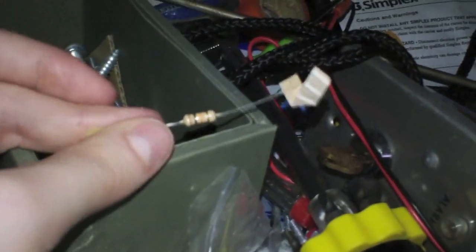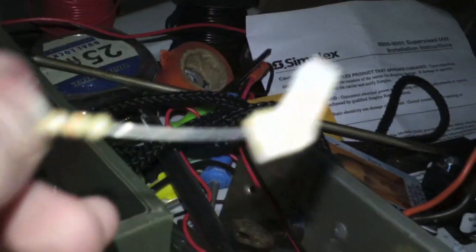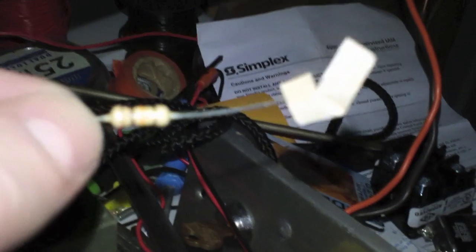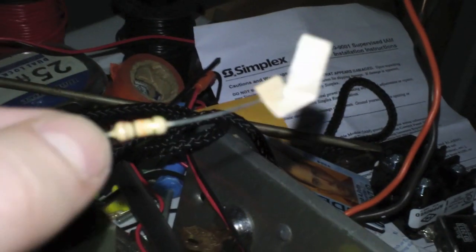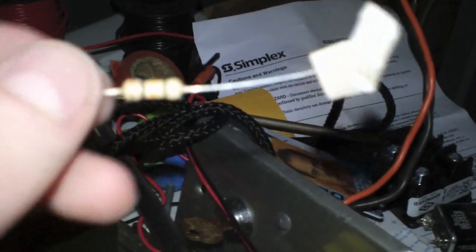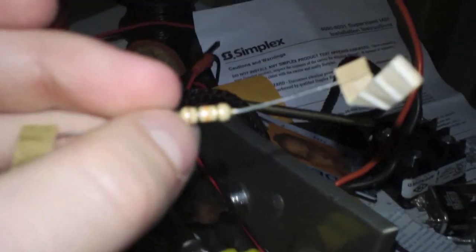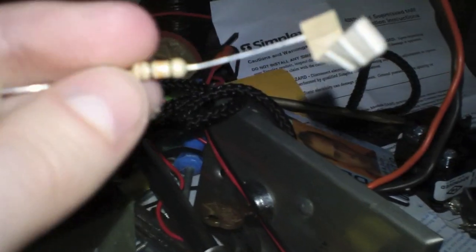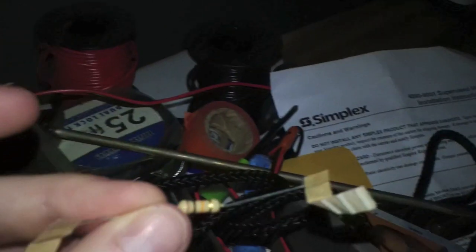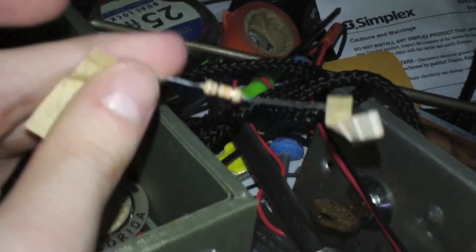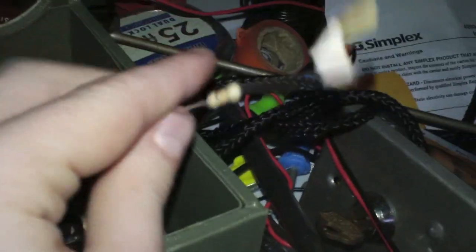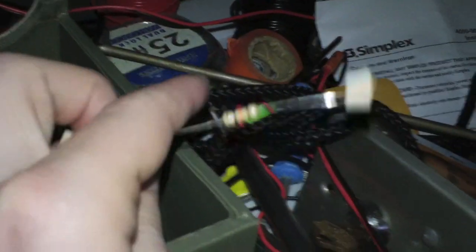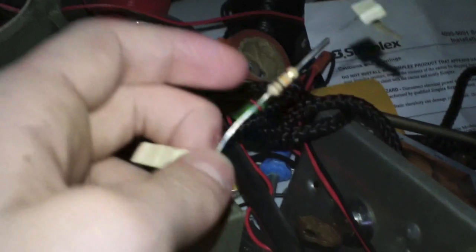And how I can tell that is by the little colored stripes on the resistor. There's a brown, a black, an orange, and then there's gold. Don't worry about the gold. Worry about the first three colored stripes. I will make a video in the future explaining about the different resistors. Those resistors help close off the line in a fire alarm circuit.